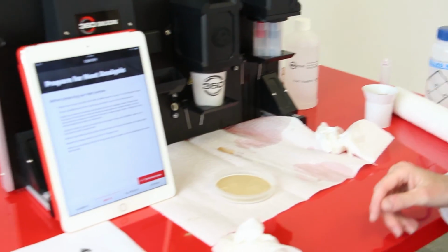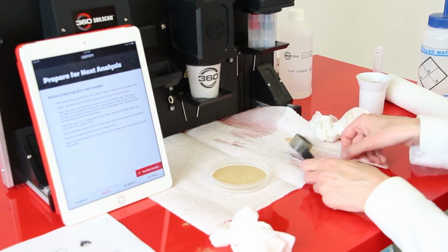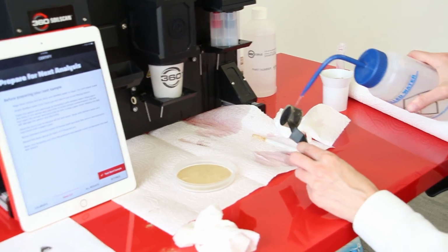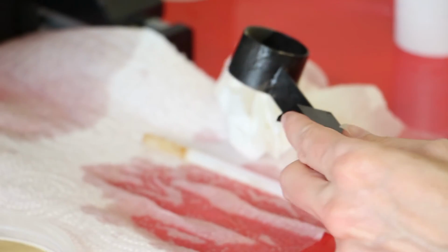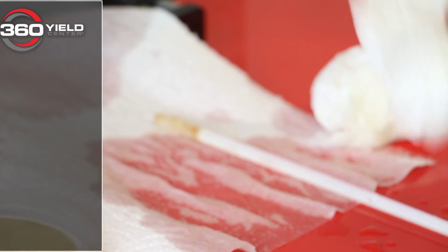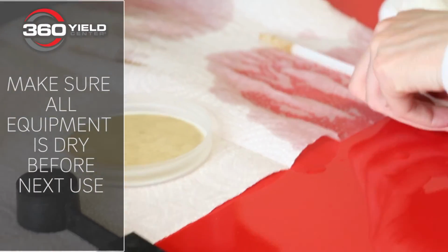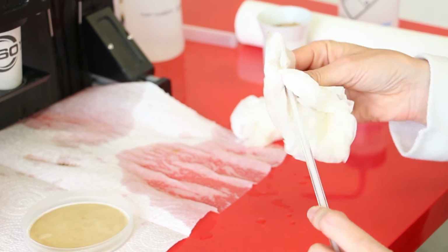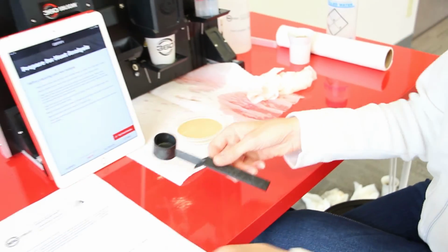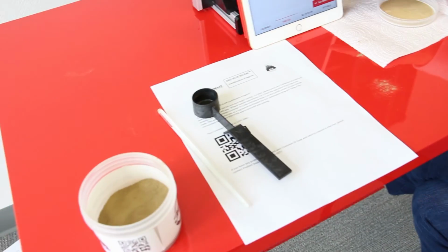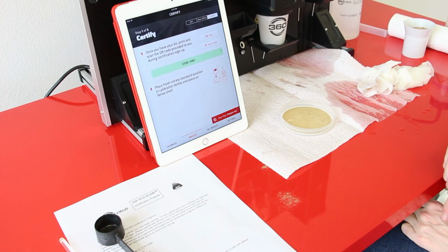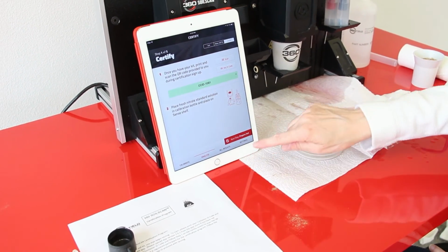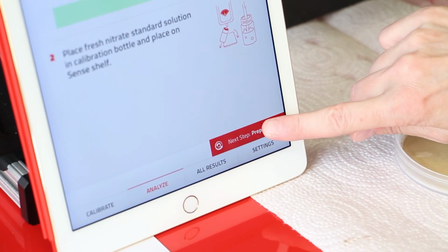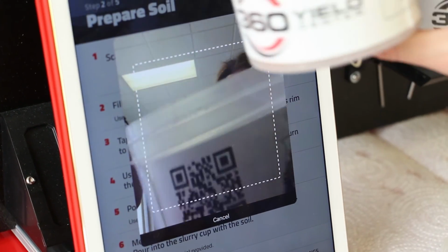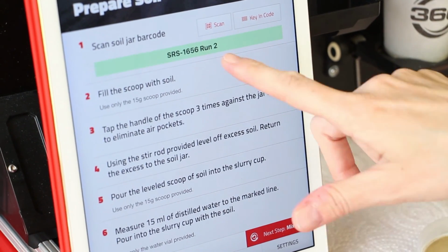So the next step that you also want to take is to make sure that you rinse both your scoop down with distilled water. If you want, go ahead and use tap water with it, and then rinse with distilled water too. And make sure that's dry before you use it on your next sample as well. And then rinse your stir stick down too. And we do this to avoid contamination on our next samples. And from there you can press test next sample. You already have your customer ID in, so you can go down to the bottom and you can hit next step. Scan your jar in, and it's going to tell you you're at your next run with it.